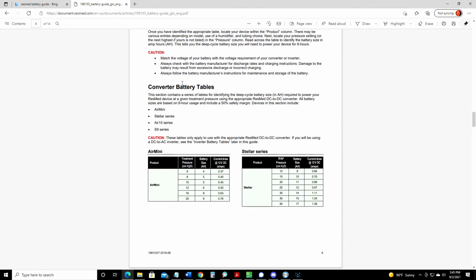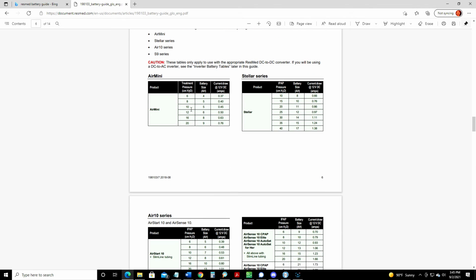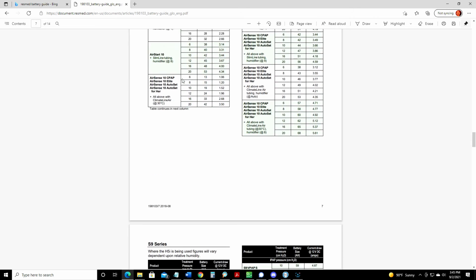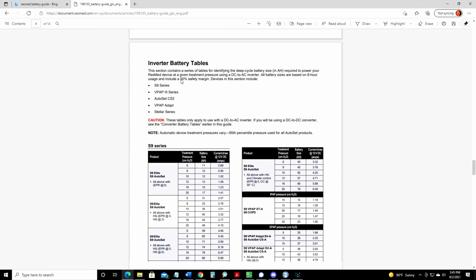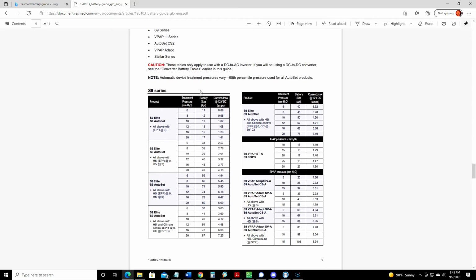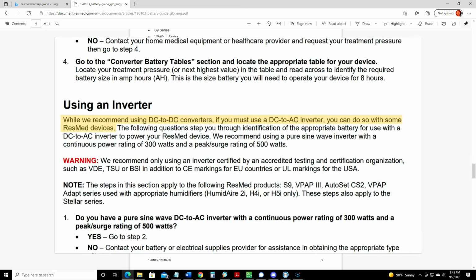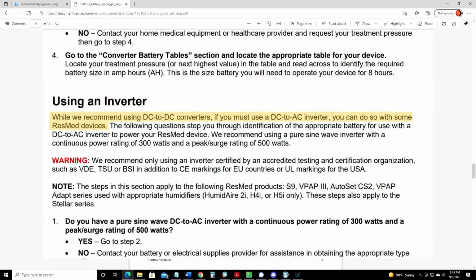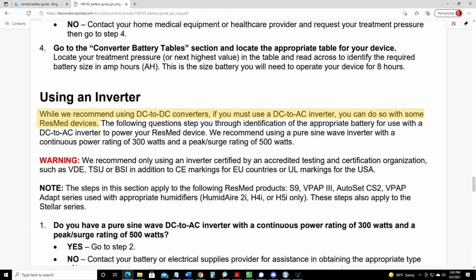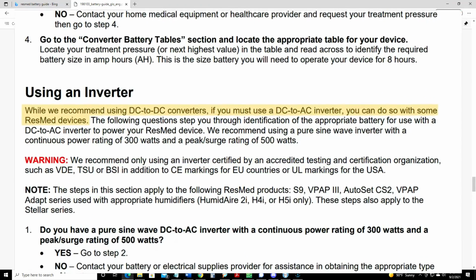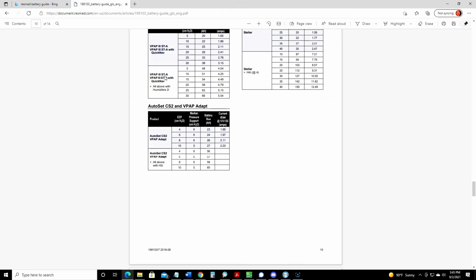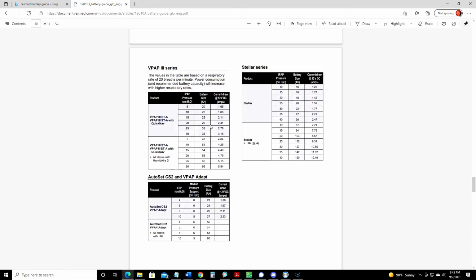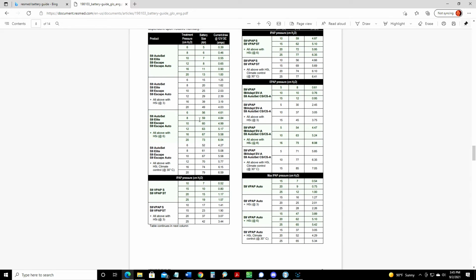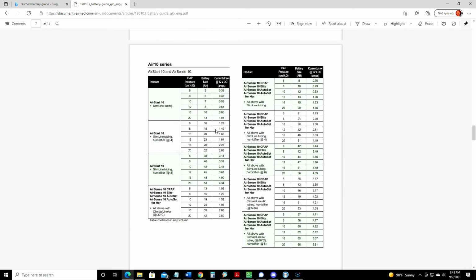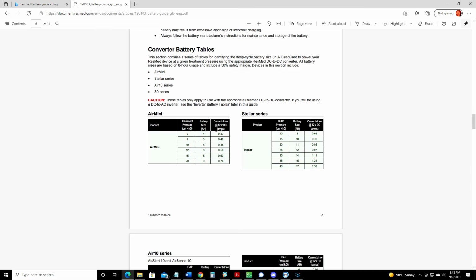Yeah, if you look down here at the converter battery tables, and that's running off of DC instead of plugging in power, you've got the AirMini, the Stellar, the AirSense 10, the S9. But if you look at the inverter battery tables, the only machines that they certify to run off an inverter are S9 series, VPAP 3, Stellar, and AutoSet CS2 and VPAP Adapt. So yeah, you shouldn't be running an AirSense 10 off an inverter, but you really wouldn't be able to get enough usage out of it anyway for it to matter.